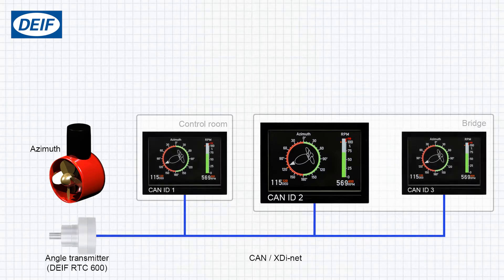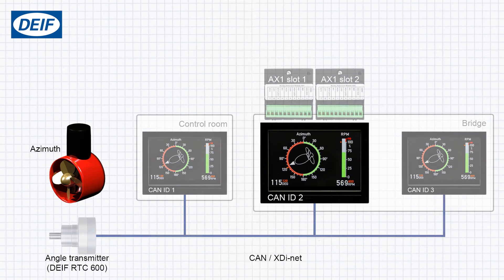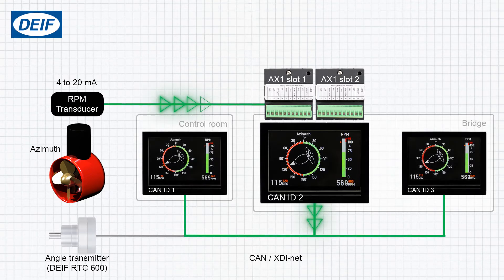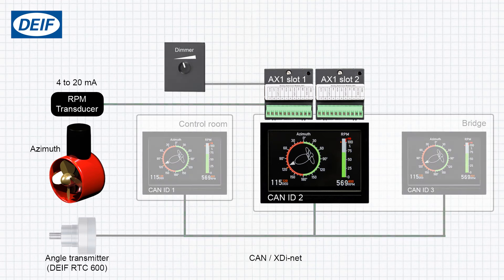A CAN transmitter is mounted on the azimuth and the value is transmitted via CAN bus to all the XDIs. The XDI has two analog AX1 modules fitted. An RPM transducer is connected to the first analog module, and the XDI transmits the RPM data to all the other XDIs over XDInet.